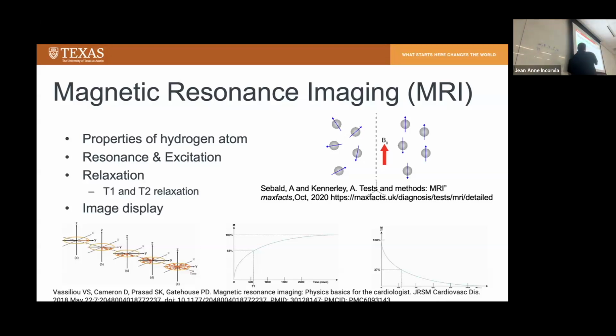If you think of a grid of all the hydrogen atoms, and each one has a spin in a different phase, basically the MRI takes that grid and has a gradient coil that changes the phase of the rotating hydrogens to create stripe patterns by controlling how long the X and Y gradients are turned on. And they measure the phases in all different frequencies and orientations to produce an image.